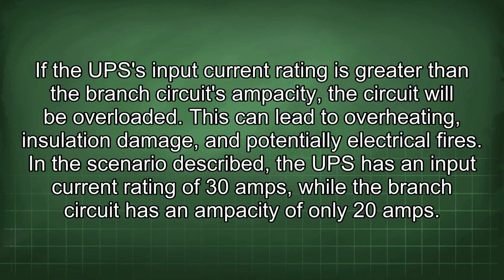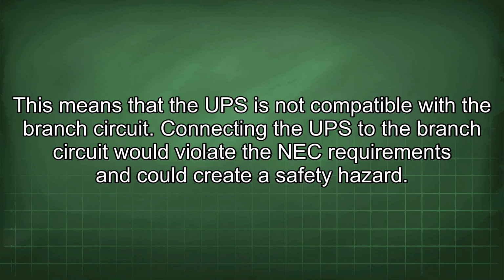In the scenario described, the UPS has an input current rating of 30 amps, while the branch circuit has an ampacity of only 20 amps. This means that the UPS is not compatible with the branch circuit. Connecting the UPS to the branch circuit would violate the NEC requirements and could create a safety hazard.